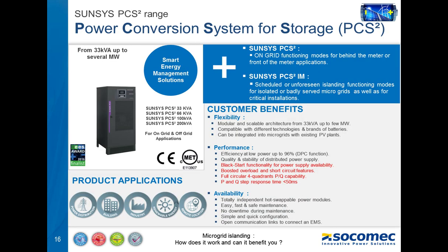To sum up all of what I just said, what is important to keep in mind is that our machines are available from 33 to 200 kVA to answer on-grid applications, but also on- and off-grid applications in case of the PCS2 IM version. In this latter version, we introduced some key features, such as the black start functionality that enables to power an untied microgrid. We also introduced some boosted overload and short circuit features, preventing to oversize the installation. The products also have full circular 4 quadrants PQ capabilities, and the PQ response time are lower than 50 milliseconds.